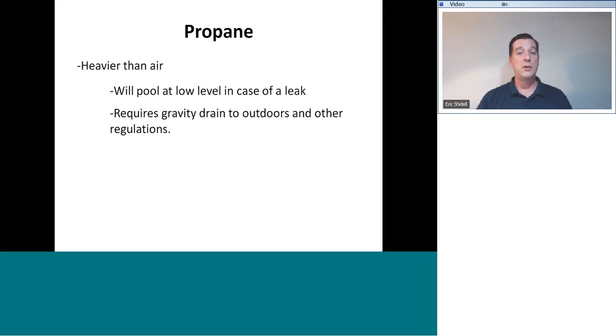You'll go to the lowest point in the building, either basement or crawl space, and find that propane gas safety shutoff device. And be careful, because there's a darn good chance that it responded like it was supposed to, meaning there's a leak in the system. There's a leak somewhere. So don't be having cigarettes, or using your torch or a lighter. Be careful of sparks, and use your nose, because there's odorant in those gases.